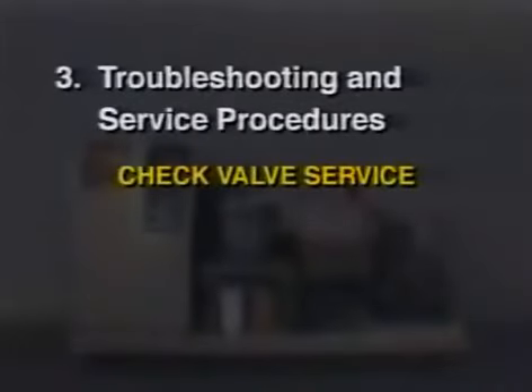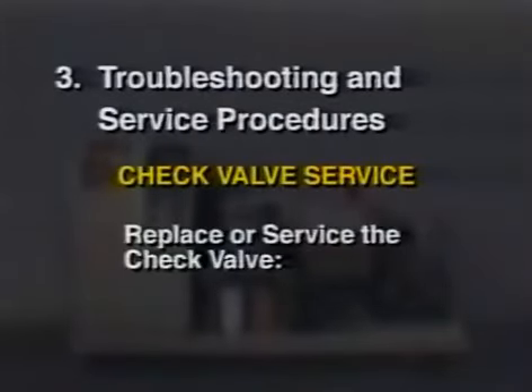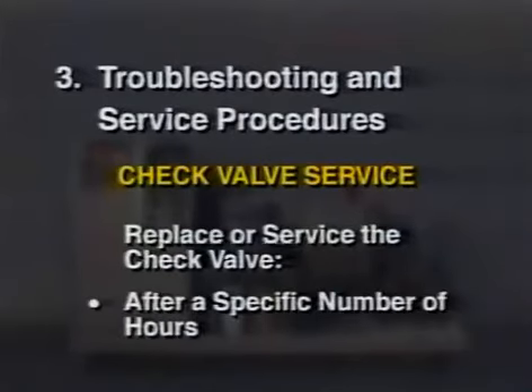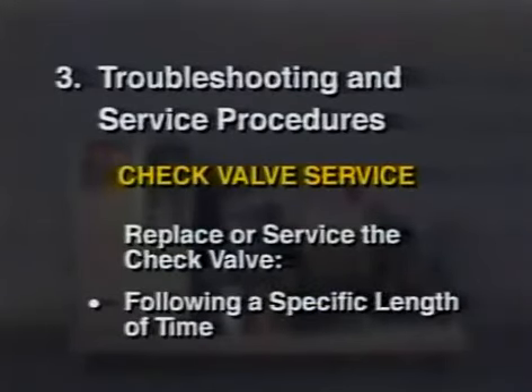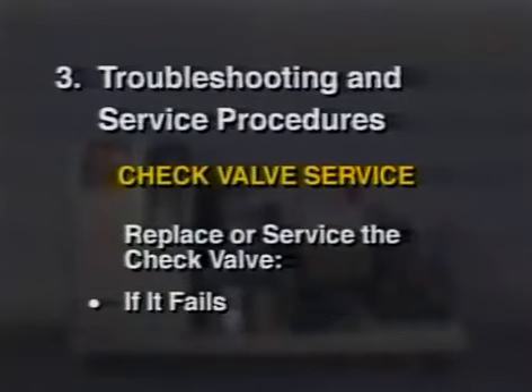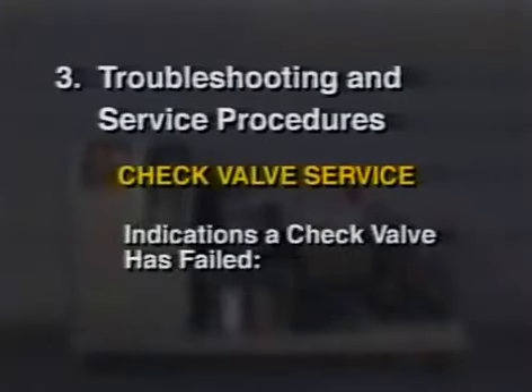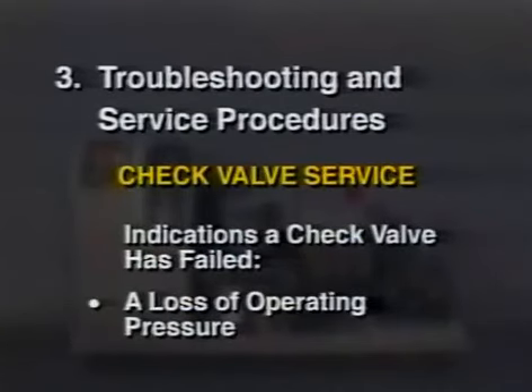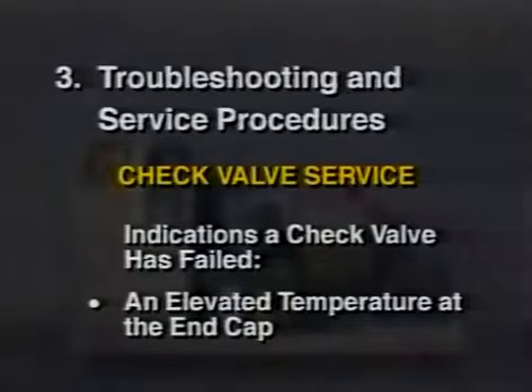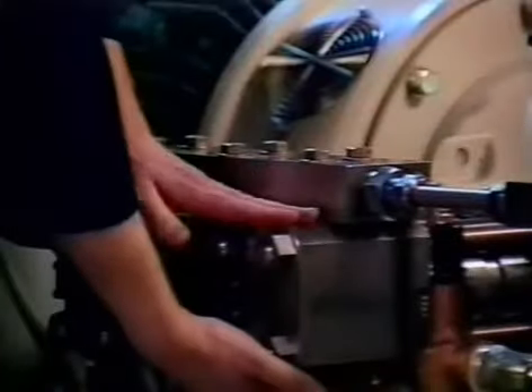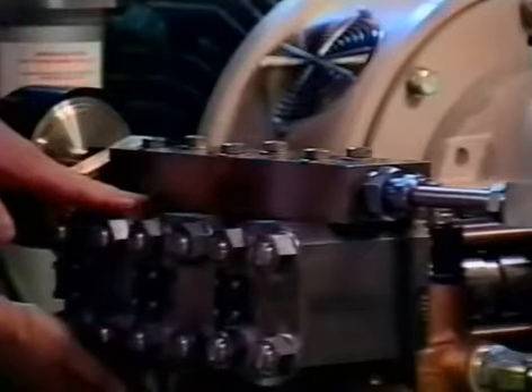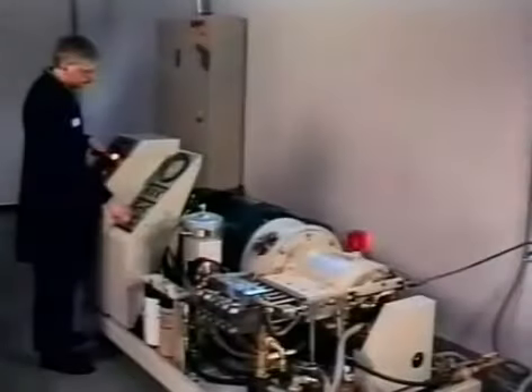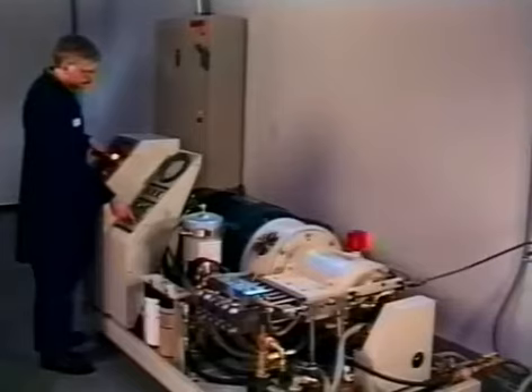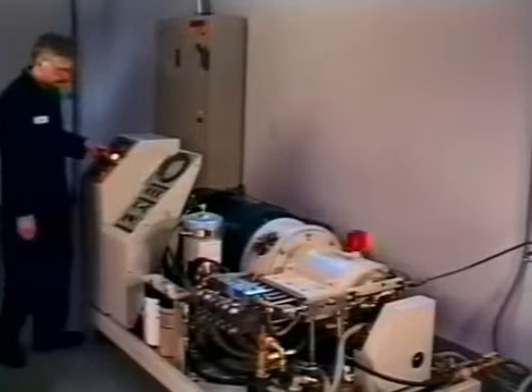Check valve service. Replace or service the check valve after a specific number of hours, following a specific length of time, or if it fails. There are two indications a check valve has failed: a loss of operating pressure and elevated temperature at the end cap. This increase in temperature is first noticeable on the underside of the end cap, near the accumulator. To replace or service a check valve, first shut down the system. Make sure the pressure is bled down.